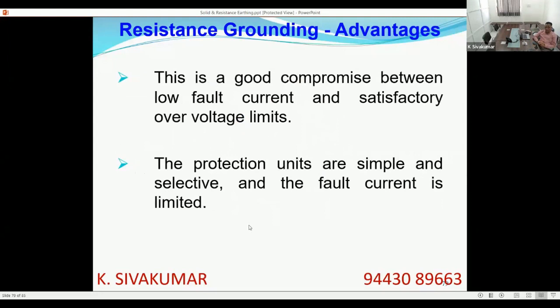Advantage of a resistance grounding system: it is a compromise between an unearthed system and a solidly earthed system. In a solidly earthed system, fault current is high; that is overcome by the low fault current. In an unearthed system, because of resonance between reactance and system capacitance, over voltages are possible. Here the zero sequence path is made resistive, so there are no chances of resonance. So over voltages are reduced.